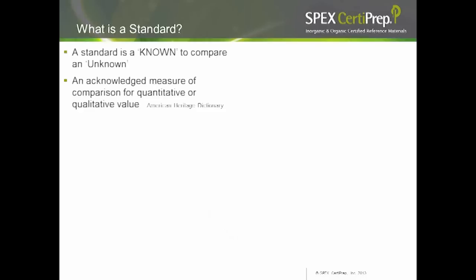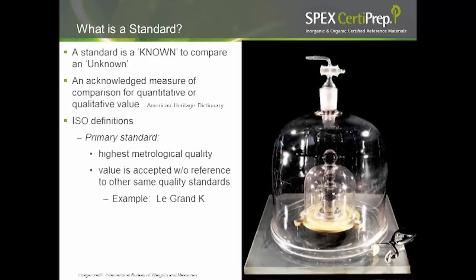Now if we look at the alphabet soup of terminology, we'll start with the first question: what is a standard? The simplest answer is that it is a known compared to an unknown, or it is an acknowledged measure of comparison for a quantitative or qualitative value. ISO designates a primary and a secondary standard. A primary standard is the highest metrological quality, and its value is accepted without reference to a similar quality standard.